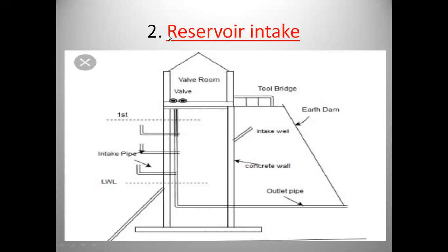The second type of intake is reservoir intake, constructed at the reservoir. The reservoir intake has three intake pipes because the water level in the reservoir changes gradually. At the valve room, valves are provided to control the flow of water in the intake pipes. A concrete valve tower is constructed for the reservoir intake. A foot bridge or tool bridge is used to access the valve room to control the valves. An intake well is constructed to intake the water, and from the outlet pipe, water from the reservoir intake goes to the water treatment plant.